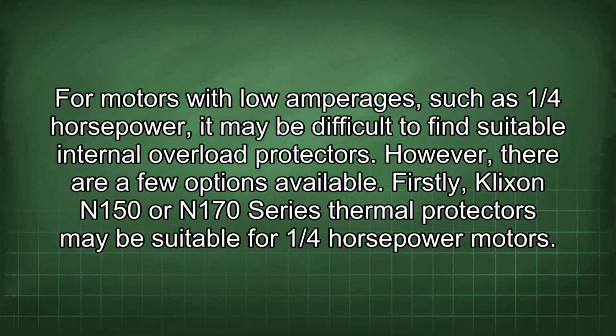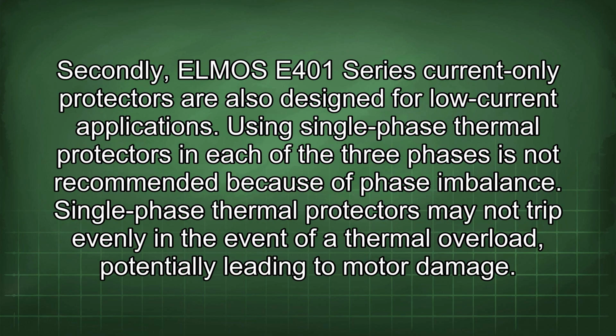For motors with low amperages such as 1/4 horsepower, it may be difficult to find suitable internal overload protectors. However, there are a few options available. Firstly, Klixon N150 or N170 Series thermal protectors may be suitable for 1/4 horsepower motors. Secondly, ELMOS E401 Series current-only protectors are also designed for low current applications.